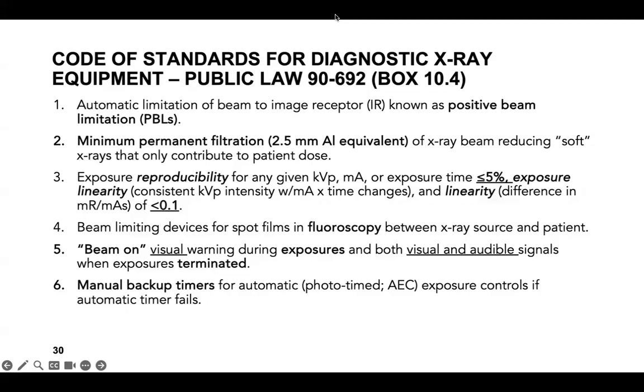Exposure reproducibility for any given kVp, mA, or exposure time, less than or equal to 5%, exposure linearity, a linearity difference of less than 0.1. Beam limiting devices for spot films and fluoroscopy between X-ray source and patient. Beam on visual warning during exposures, and both visual and audible signals when exposures are terminated. So basically, what that number 5 is, when we're supposed to have a sign outside of our X-ray room that tells us when the X-ray is in use. So making sure that you actually have it in place and it does work. That's one part of that. And then manual backup timers for automatic photo timer AEC exposure controls if the automatic timer fails.